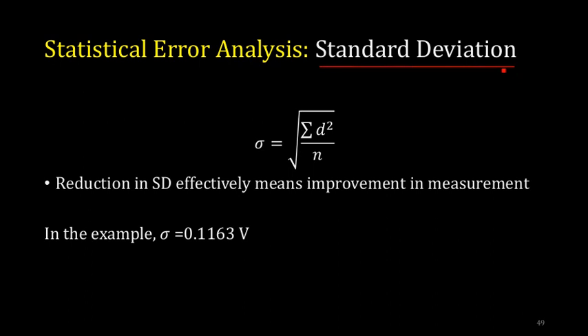Standard deviation is a statistical tool we are already familiar with. You take the square of each deviation, sum them, take the average, and then take the square root. Using this equation you get the standard deviation. A lower standard deviation means your measurements are improving. From the example, the standard deviation calculates to 0.1163 volts for a 100 volt nominal value.